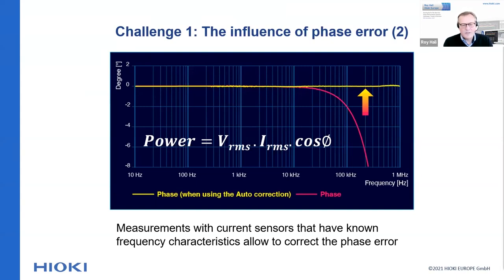The current measurement is different, however. All different current measurement methods create phase errors. Internal shunt resistors, for instance, have a low resistance and are by nature inductive, which makes them unattractive for high frequency measurements. And as we have seen earlier, the trend in power electronics is to increase the frequency and to make downsizing and improved efficiency possible.